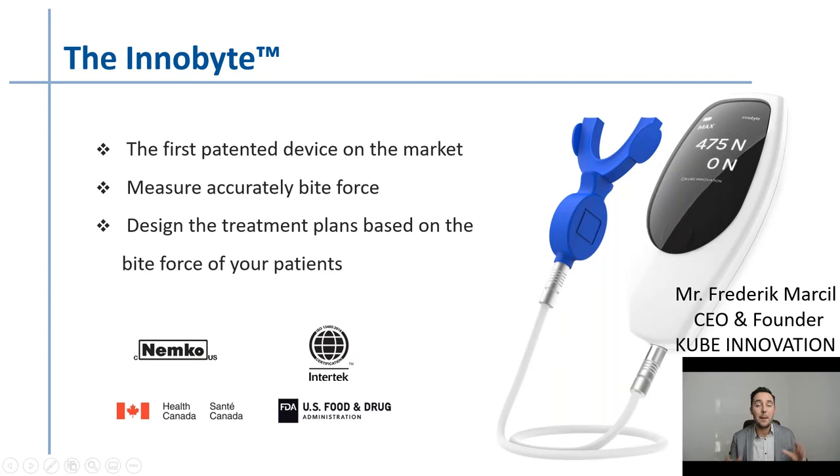Innobyte is the first patented device on the market that measures the accuracy of bite force and designs treatment plans based on the bite force of your patients. It's Health Canada certified first, and then FDA certified. What you see here — the blue part is what the patient bites down on. It's truly a bite force register. On the side you can see 475 Newtons — that's the patient's bite force.